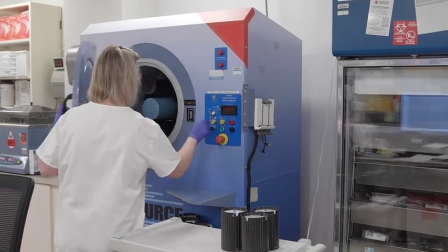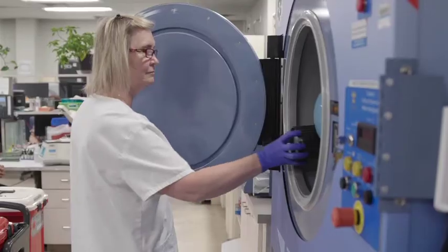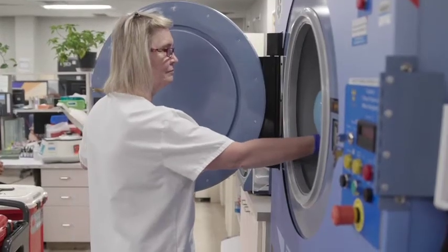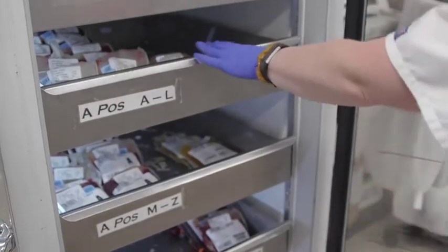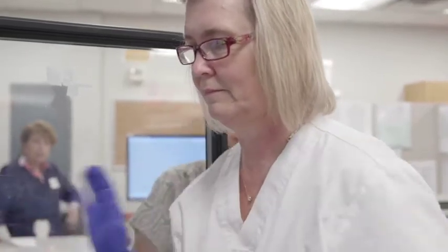Using the same calculus about risk to the organization and the requirements around having a cesium irradiator, we felt that the best decision was to use X-ray irradiation in the blood bank to protect our patients from adverse effects of transfusion. Atlantic Health System, Morristown Medical Center, which is one of its campuses, is basically a trauma center. It's very important that it runs 24-7 and that blood is available 24-7, so throughput is very important. With the X-ray irradiator they could irradiate about six products or units at a time, but with the cesium irradiator it was only one to two products or units.